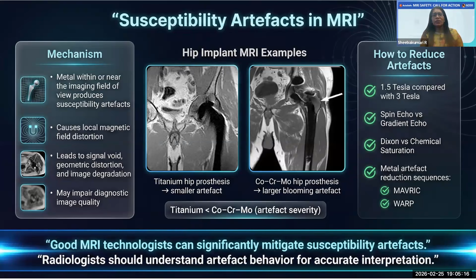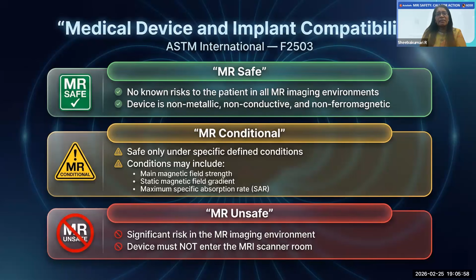Coming to the classification of implants, the American Society for Testing and Materials classified all the implantable devices into three categories: MR safe, MR conditional, and MR unsafe. An MR safe item is non-metallic, non-conductive, and non-ferromagnetic, and poses no potential risk to the patient in all MR imaging environments. MR conditional means they are safe only under defined conditions, and MR unsafe means the item poses significant risk in the MR environment, and we should not take it into the MR room.